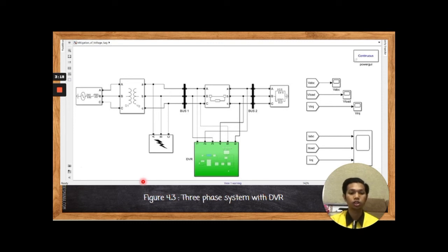The DVR, which is serially connected to the network through the injection transformer, adjusts voltage from several PQ issues like sag, swell, harmonic, and voltage imbalance at loading terminals. The fundamental concept of the DVR is that the voltage of the requested size and frequency can be restored even if the source voltage is imbalanced or distorted, to the proper waveform amplitude.